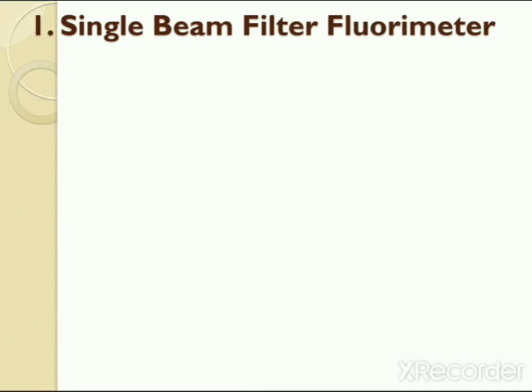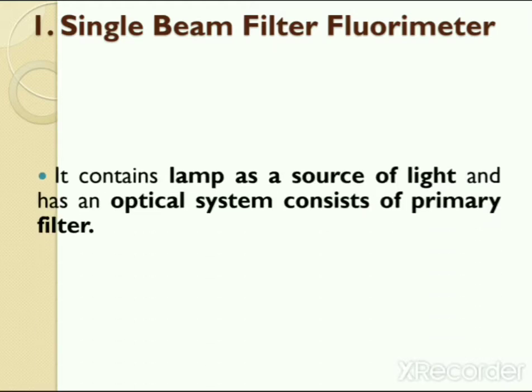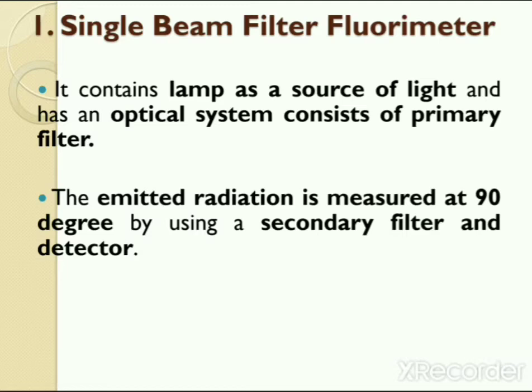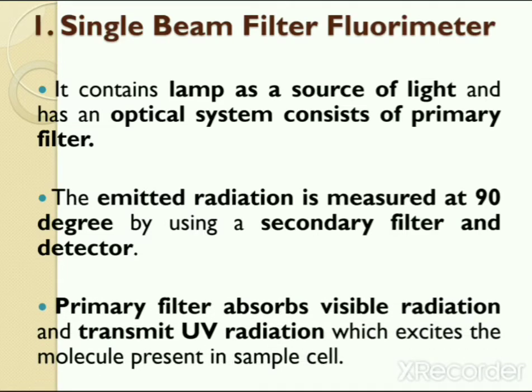The first type of instrument is the single beam filter fluorimeter. As the name suggests, this type of instrument utilizes a single beam of light for fluorimetric analysis. This instrument consists of a tungsten lamp as the light source, and for selecting a specific wavelength it also contains an optical system as a primary filter. Emitted radiation is modulated to a 90 degree angle and then passes through a secondary filter and is analyzed by the detector. The primary filter absorbs visible radiation and transmits ultraviolet radiation, while the secondary filter absorbs ultraviolet radiation and transmits visible radiation produced by the sample.